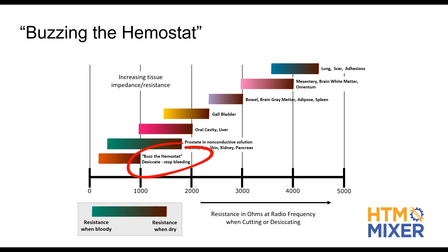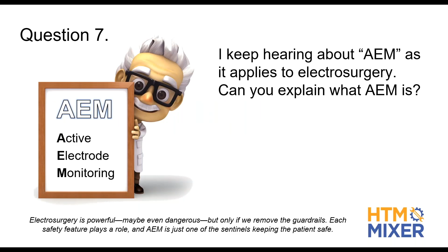Students have told me over and over that a hospital bought a device that monitors the ESU output for safety, called an AEM. In reality, there is no standalone safety box for this. The truth is AEM is built in — built into the generator, like the FT10, and built into the instruments as well. AEM stands for active electrode monitoring. The generator has internal monitoring circuitry, and the instruments have a conductive shield and an RFID chip. If you're using LigaSure and FT10, it has an RFID chip that identifies the kind of instrument — and RFID is also used for anti-counterfeiting. Together they shut down the power if stray current is detected. So it's technology built within. At the bottom end, no shield, no chip, no protection.